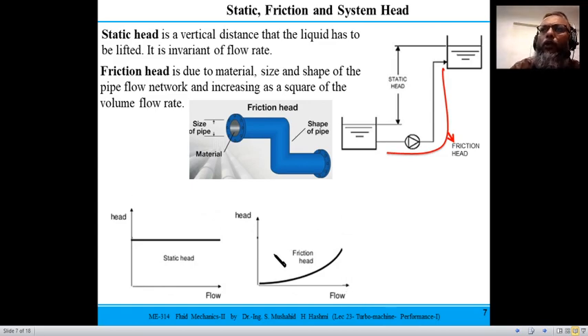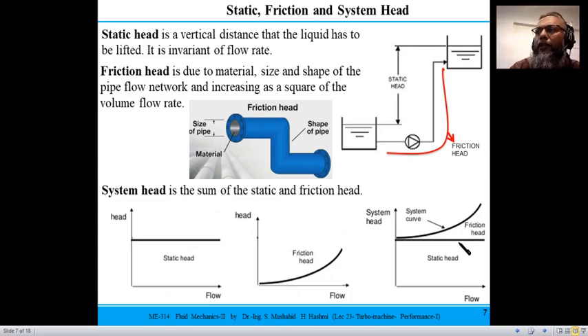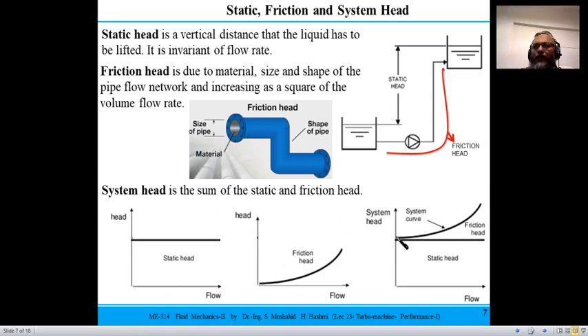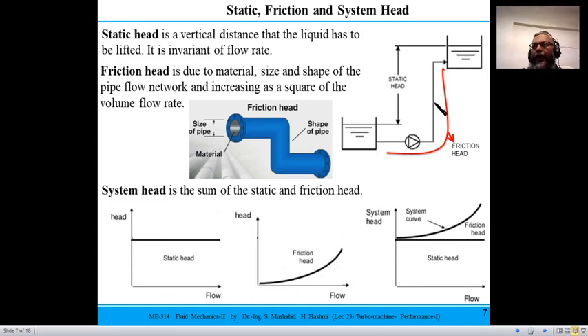Static head is independent of volume flow rate, while friction head is proportional to it. Combining them by superimposition gives the system head — also called total head — which increases with flow rate. The system head represents what the pump must provide: first the static head to raise the water level, plus the friction head to overcome pipe resistance.